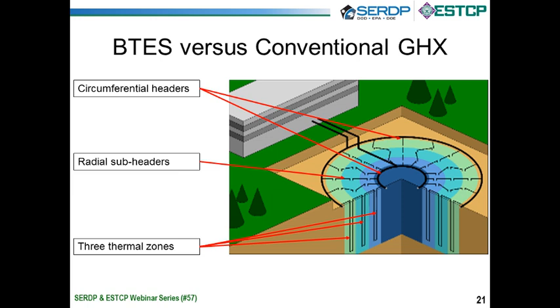This illustration, I hope, is a little bit helpful and kind of gives you an idea of what we have here. So starting at this location, this main is, in the case of discharging the BTES, the supply main. So water is flowing here into the BTES through this outer circular or circumferential header running around the perimeter of the bore field. And then the water flows from that header down through a series of three boreholes in increasingly colder zones. And then the coldest water flows through another smaller circumferential header and back to the building.